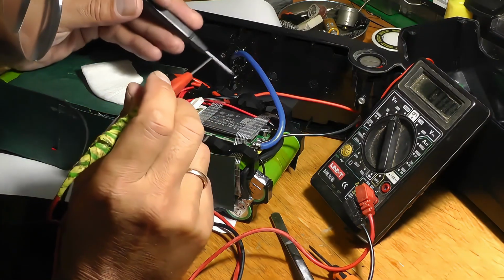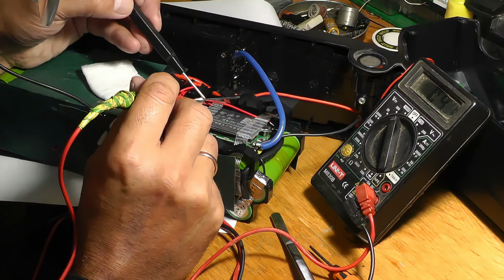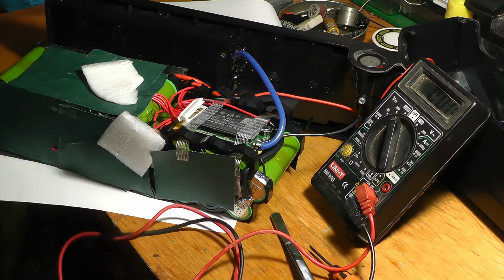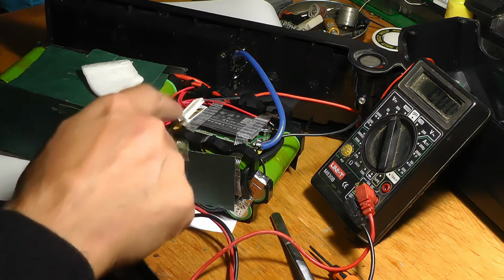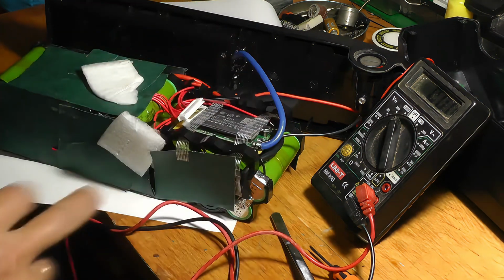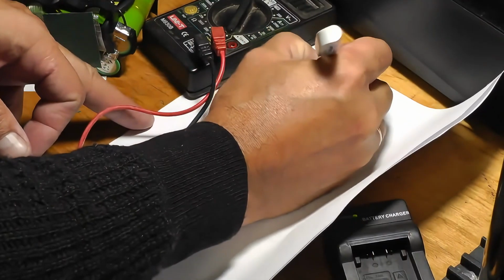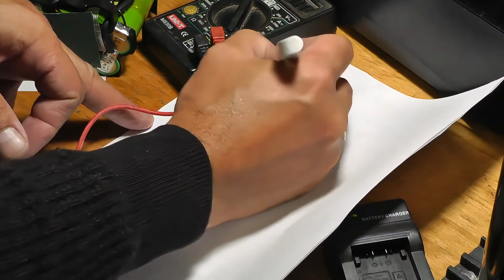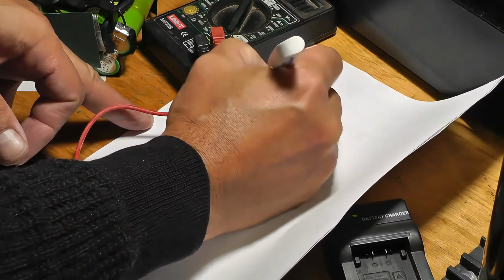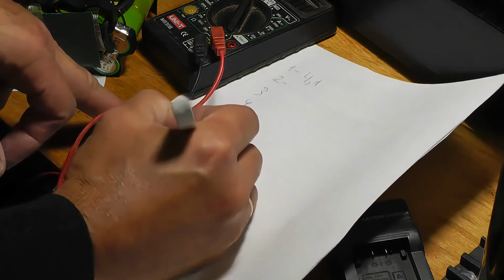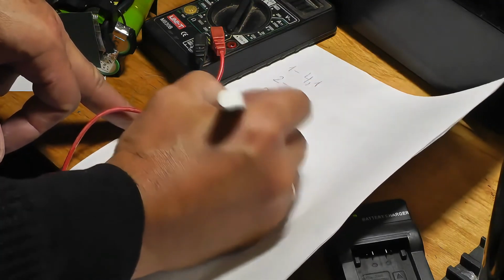Measure the voltage between the black and the first terminal. This voltage should increase each time by the same amount. This way we check each pair without removing the block, recording the numbers as we continue checking between the battery blocks.